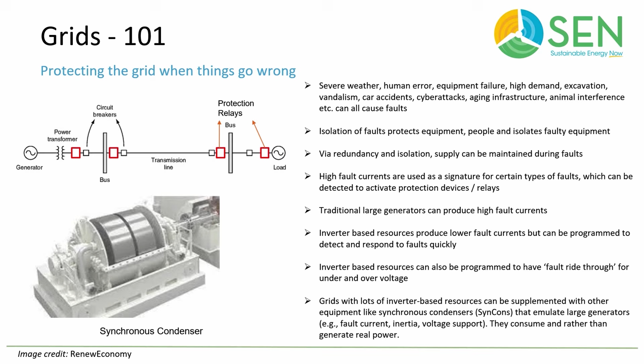Inverter-based resources like wind, solar and batteries produce lower fault currents, but can be programmed to detect and respond to faults. So grids need to be able to operate during fault conditions by isolating faults and not having a fault propagate through the system. Inverter-based resources can be programmed to have what's called fault ride-through, and that's a very important feature that provides robustness and avoids similar equipment responding inappropriately to a fault, and then you have an avalanche of trips under what's called a common mode failure scenario. This is a picture of a particular piece of equipment called a synchronous condenser, if you've ever wondered what they look like. They emulate large generators by producing fault current, inertia, and voltage support. They're like large electric motors, they don't burn fuel, and they can be used in larger grids with high contribution from inverter-based resources. They're being used in South Australia and elsewhere.